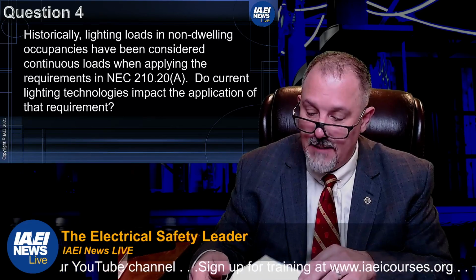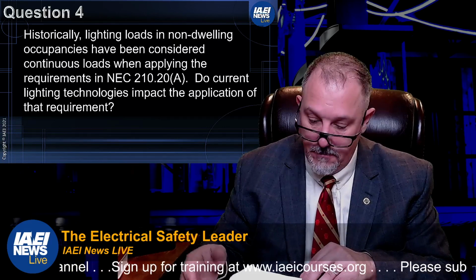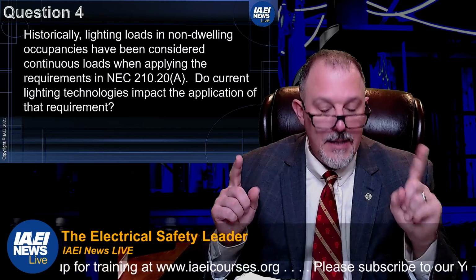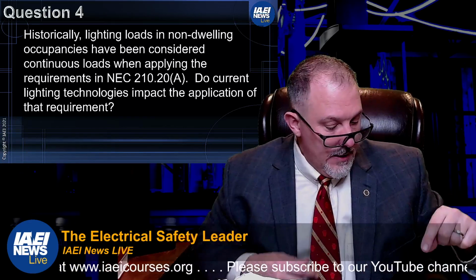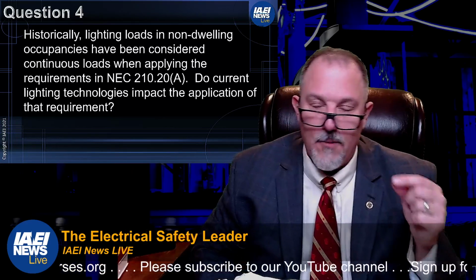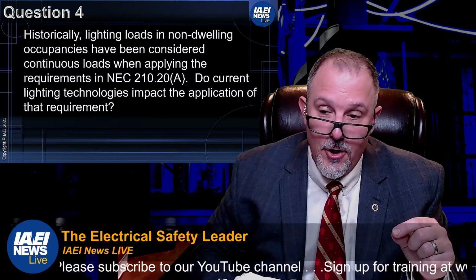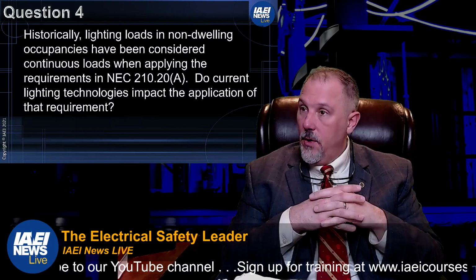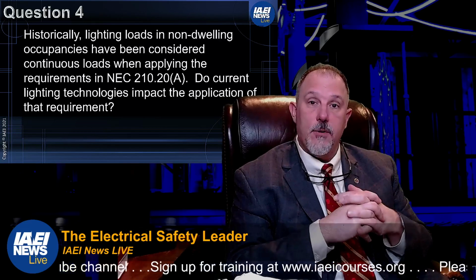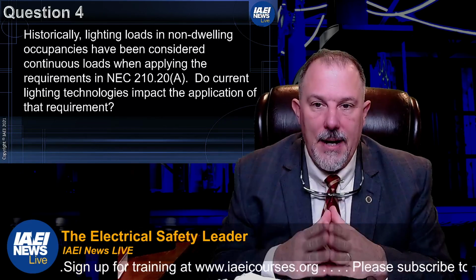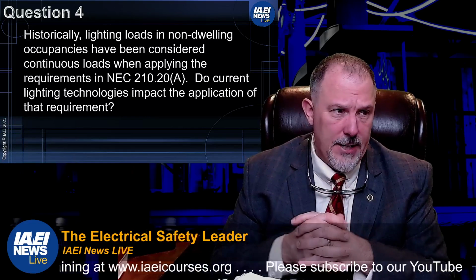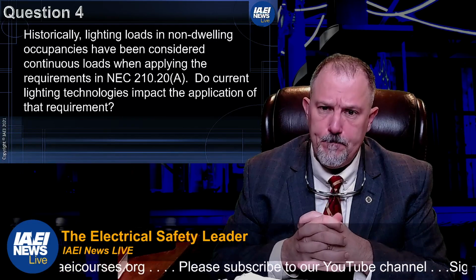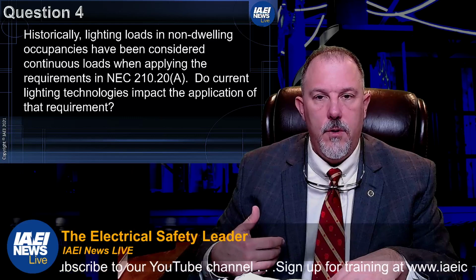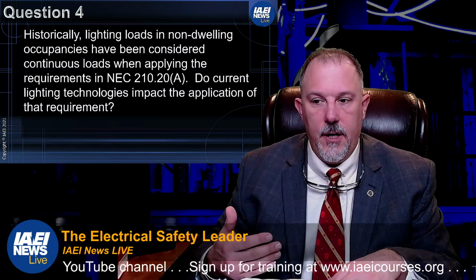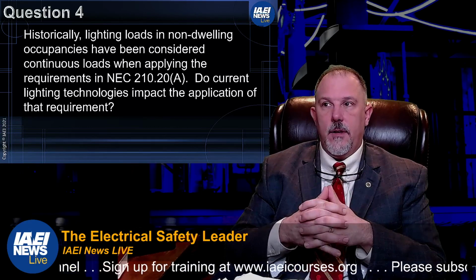But now let's think about what is a continuous load. Continuous load is a defined term. Continuous load is one that runs for 3 hours or more. So you've got to look at your lighting loads and say, will they operate for 3 hours or more? Now, you may have a discussion with a designer or an owner that says, I've installed these occupancy sensors so that when you leave the room, the lights automatically turn off. And you can say nobody is in there for more than 3 hours.